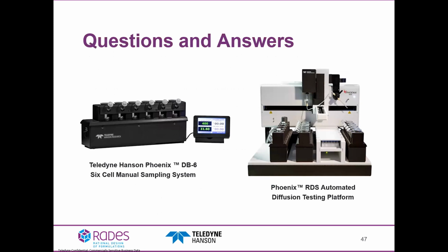Okay, back. Sasha? Okay, I mean, again, it's about providing a justification. I mean, if it's a suspension and it's suspended at 50%, 100%, and 150%, then from a theoretical point of view, you wouldn't expect a difference. Then the concentration may not be the appropriate variable to demonstrate sensitivity. Then a possibility would be that it's the particle size, for example.